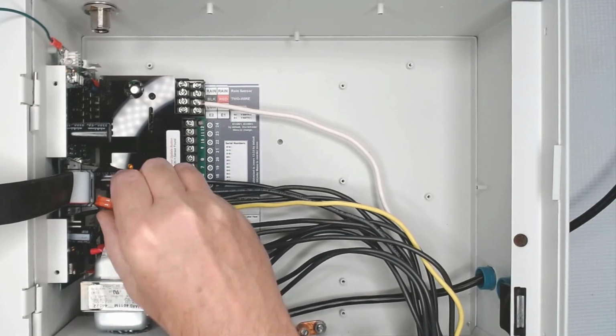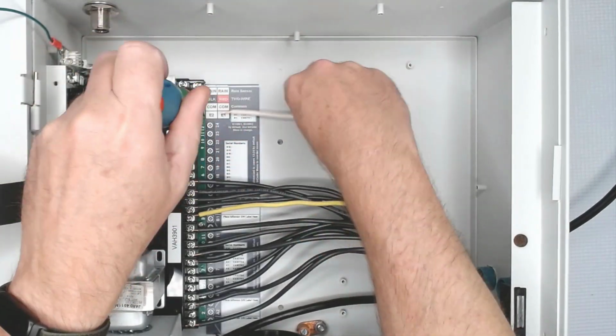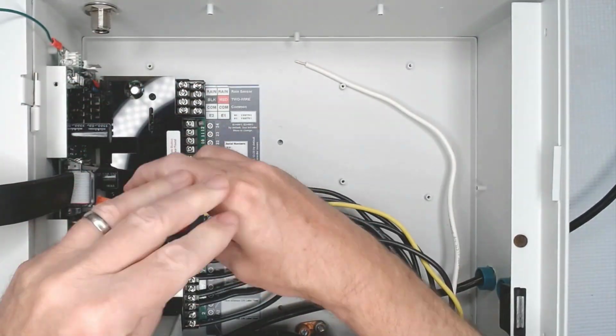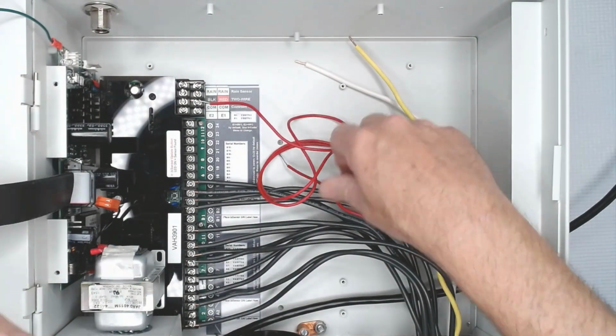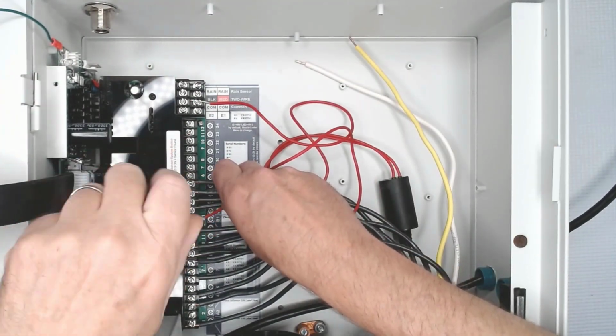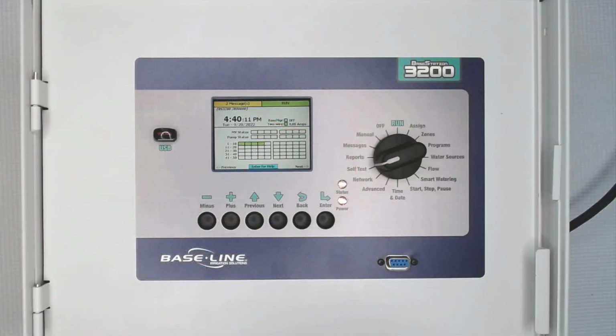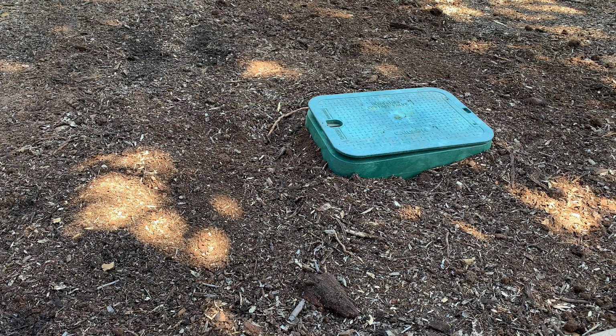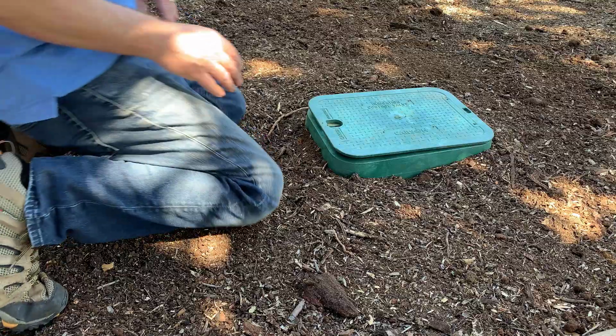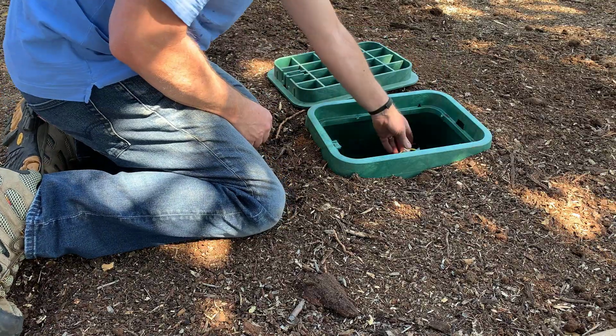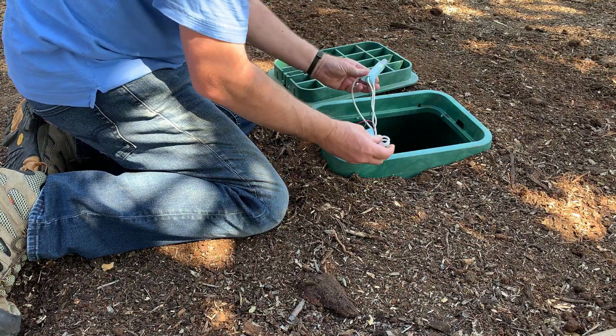Power down the controller and disconnect the valve common and one of the sensor-enabled terminals. That's A1, A2, B1, B2. Connect a known good solenoid to those terminals and test the zone. If it works, we know the powered bicoder board is good. We've taken the initial steps at the controller, so it's time to go out to the field where the soil moisture sensor is installed and inspect the wire splices.